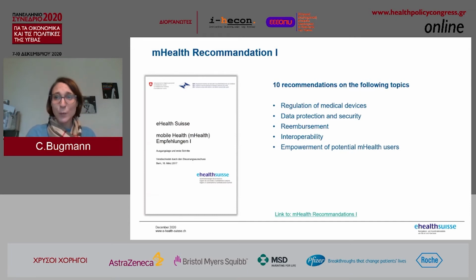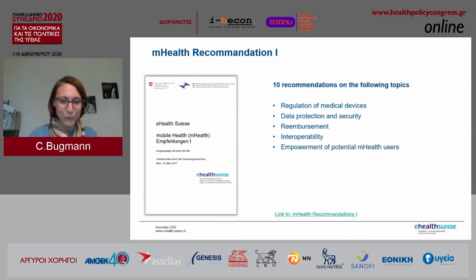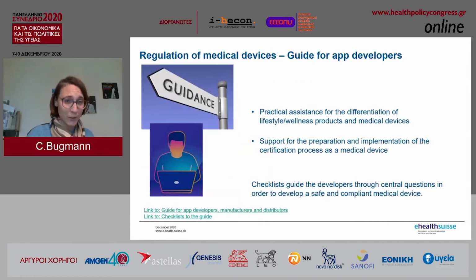I would like to present the work that we've done around these recommendations, and for that, I would like to highlight 3 of these 5 topics: regulations of medical devices, interoperability, and empowerment of potential mHealth users. To start with the regulations of medical devices, we saw that some of the app developers didn't know that their product was actually a medical device and should go through the certification process.